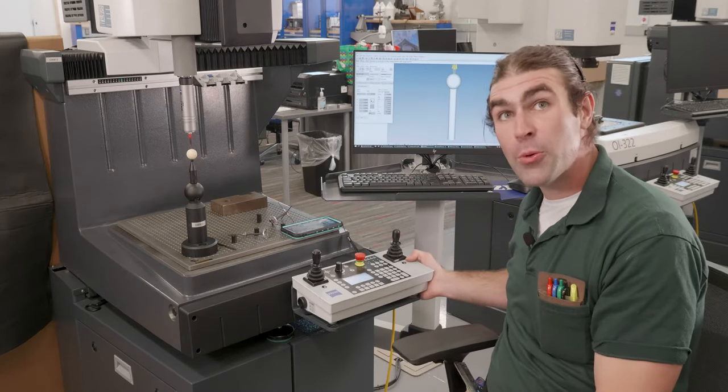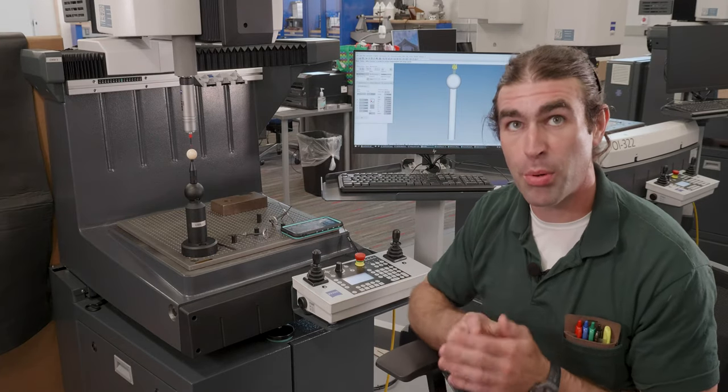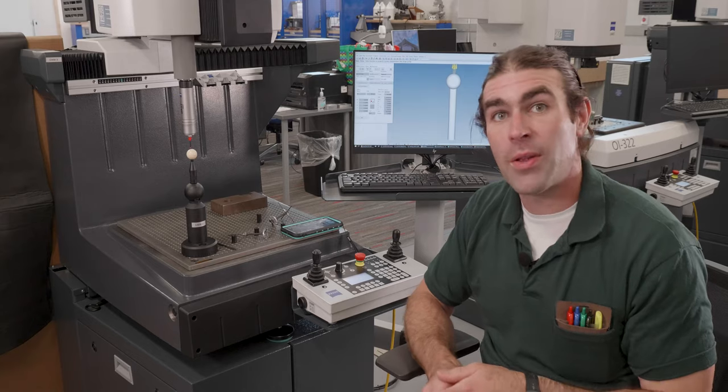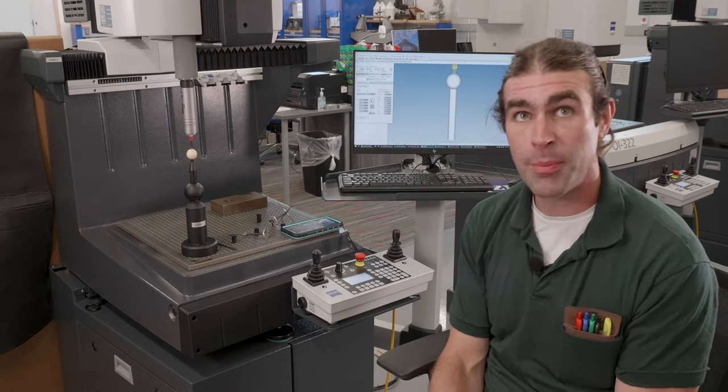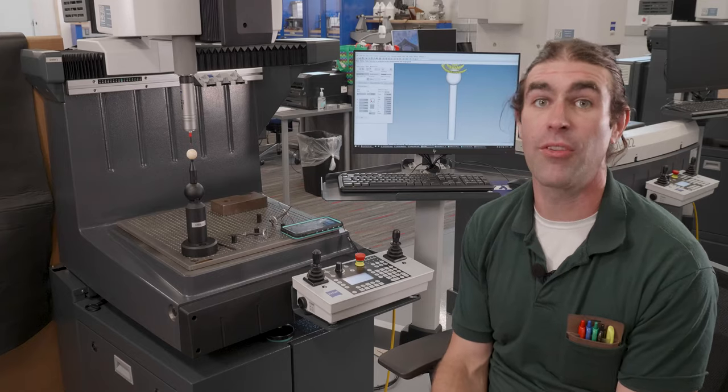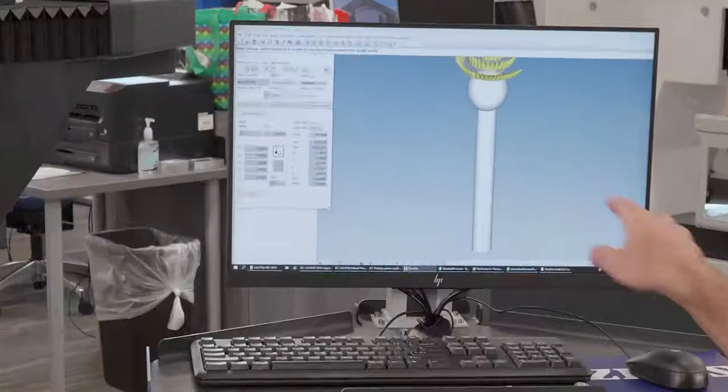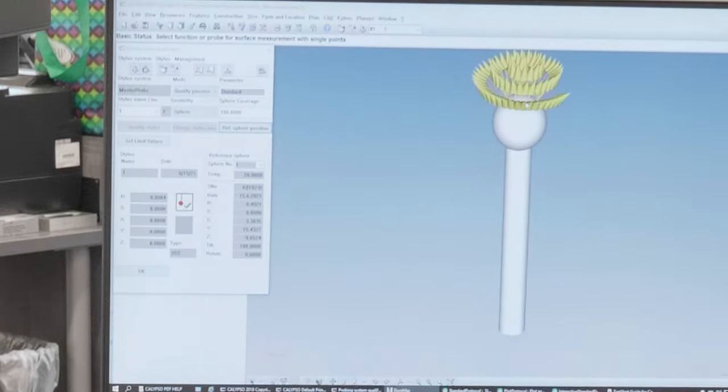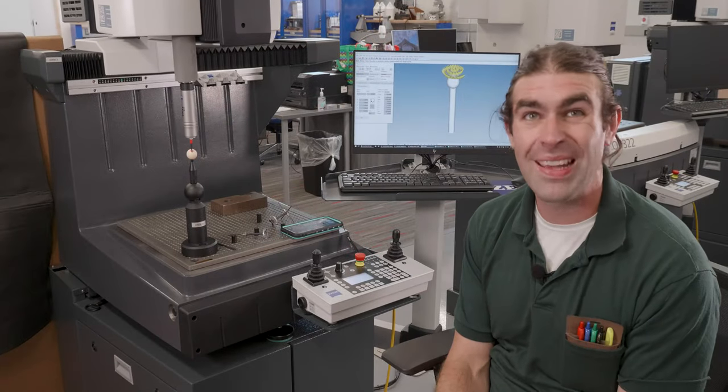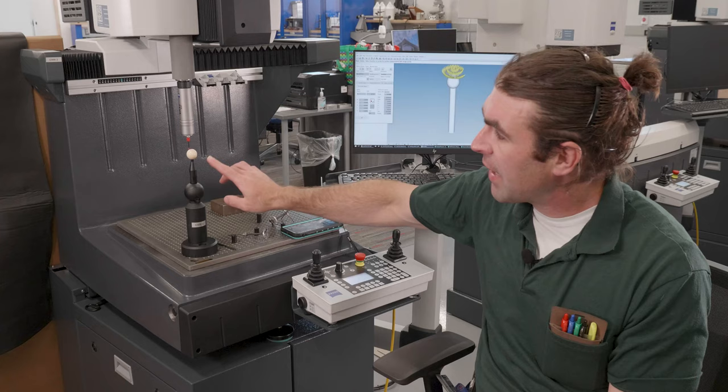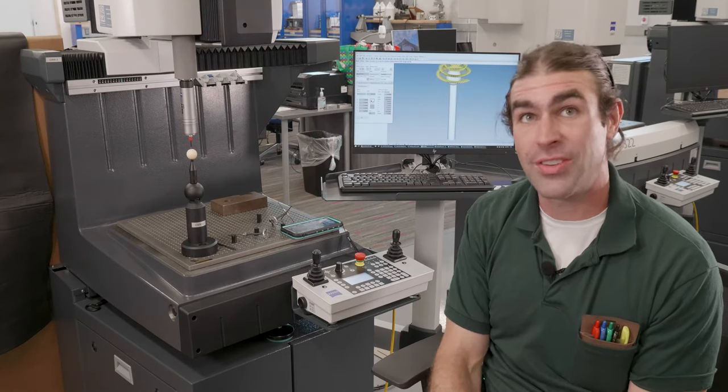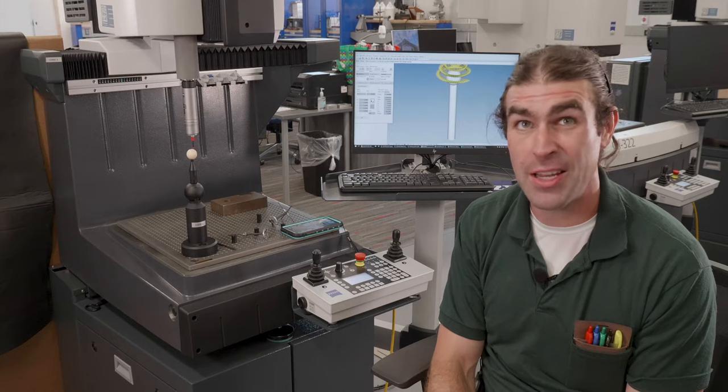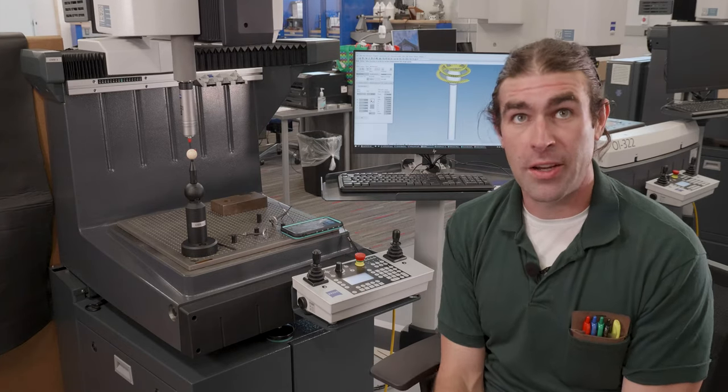So the computer is just going to do its magic. It's going to drive around. It'll take some points. It'll do some scanning. It's just figuring out where that reference sphere is and qualifying that master probe so that we can use that information for all the other stylus systems. Now you can see on the screen back here, it is showing us the points it's taking and it looks kind of cool. This process just takes a couple minutes. When it's finished, the master probe will be about an inch above the reference sphere and it just stops. It doesn't give you a dialogue or anything. It'll just be sitting there and then it'll be ready to go.